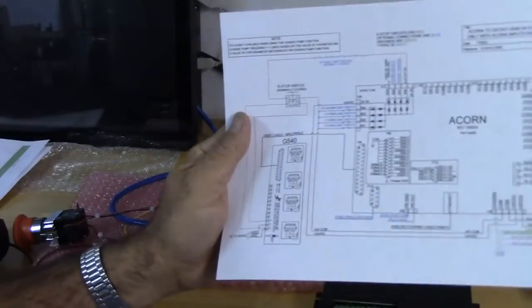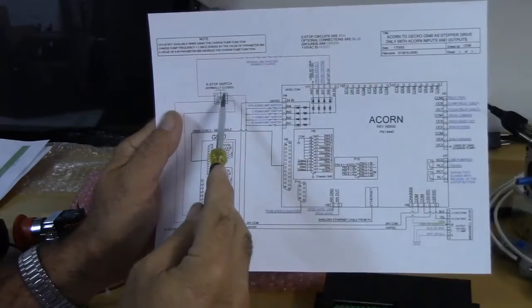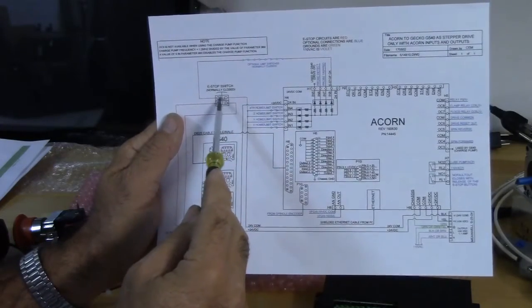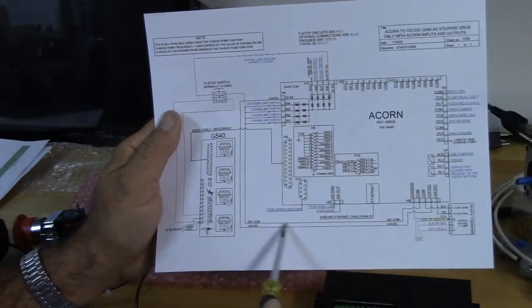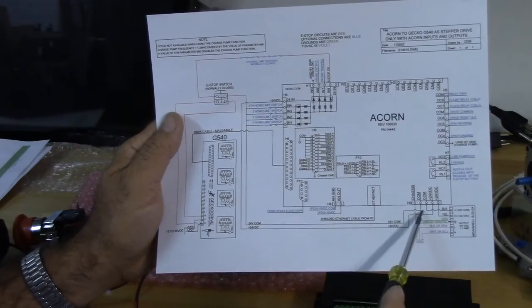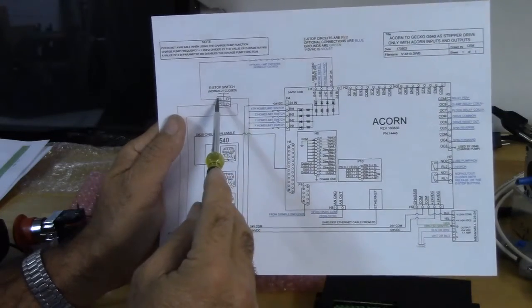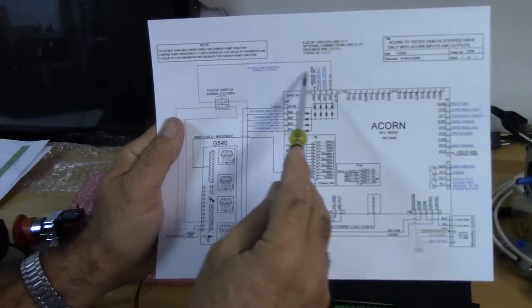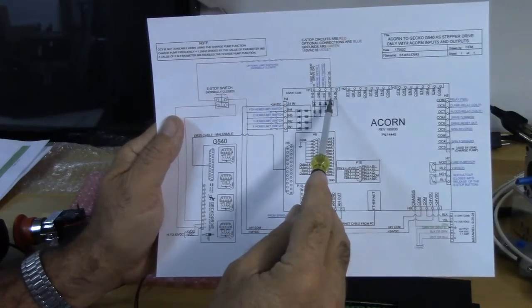Okay, so that's that part. Now we're going to wire the e-stop. We're going to run one wire per the drawing from the other set of contacts down over to 24 volts common, and the other side is going to go up, over, and down to input 8. So let's take care of the common first.